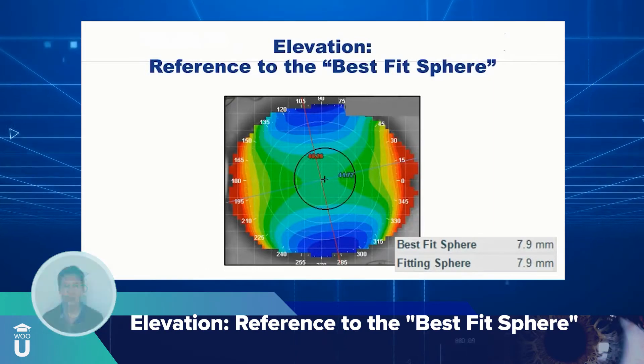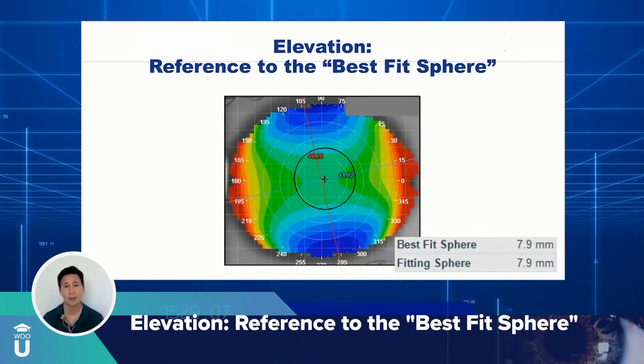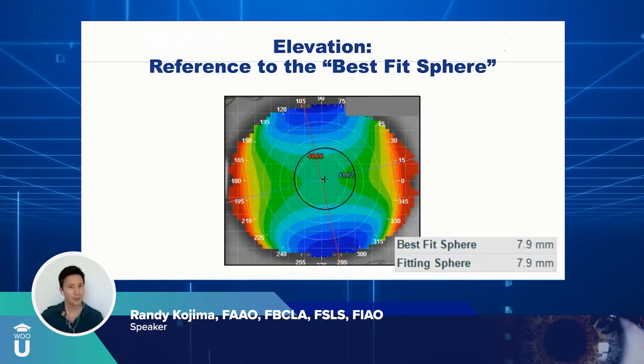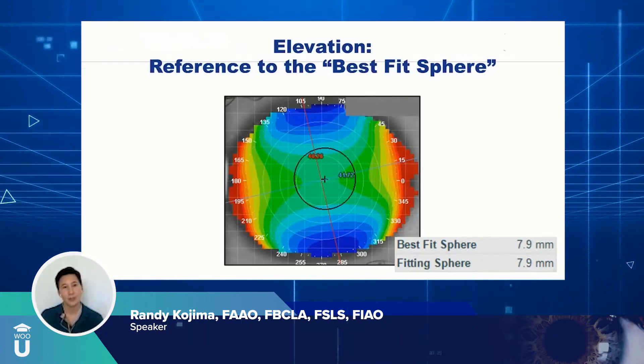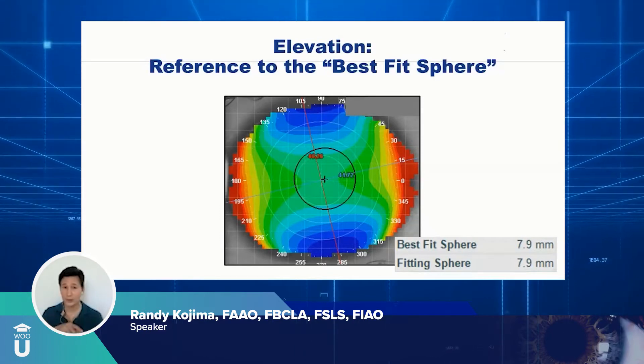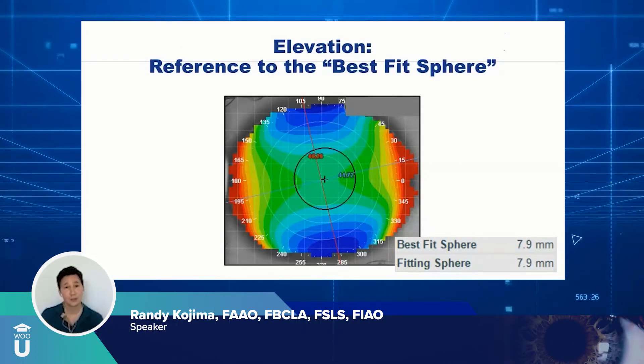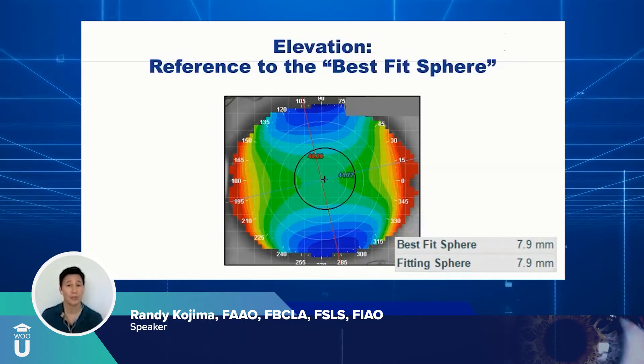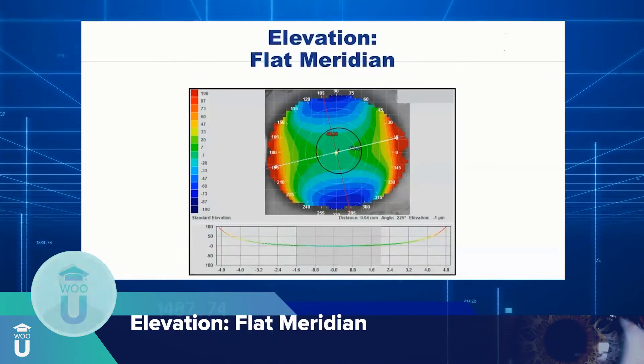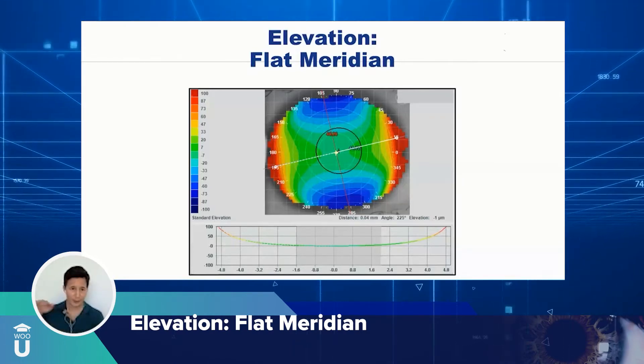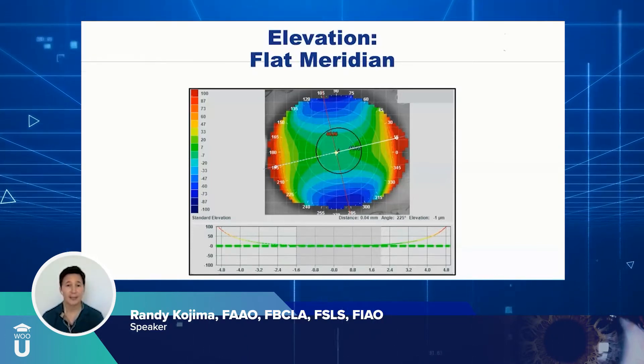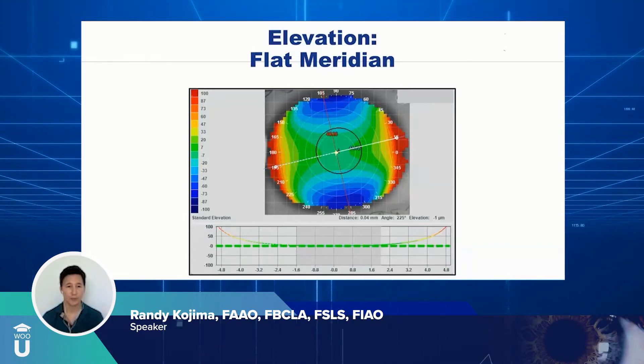To understand where those colors come from on the elevation map, it uses what's called a best fit sphere — the closest radius that will generally match the non-spherical nature of the eye. There's really no cornea you've ever seen in practice that's truly spherical. It might have a spherical K reading, but it's always slightly asymmetric in some way. The best fit sphere is the closest we can come up with. If we take the flat meridian and draw a dotted green line across the graph, that is the sphere — the perfect spherical surface.